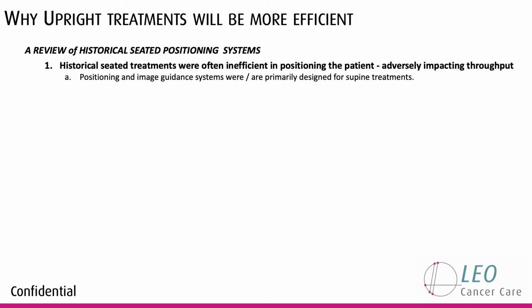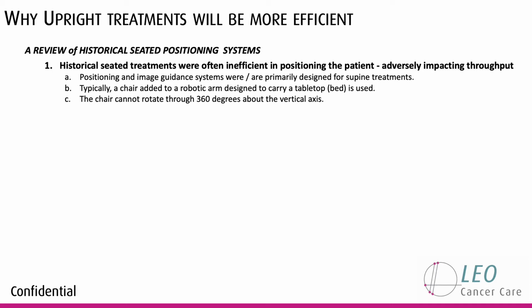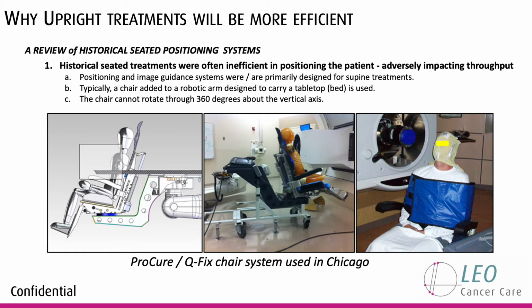And it's true that current and historical systems used for upright treatments were really basically designed for supine treatments. And so the positioning image guidance systems that they used to set the patient up had to be adapted from stuff that was designed for supine treatments. Typically a chair is added to a robotic arm designed to carry a tabletop. And I was part of many of these designs. The system that's currently used in Chicago is one of those examples. I'll show a picture of that in a minute. And the main big problem is that the chair cannot rotate through 360 degrees about a vertical axis.